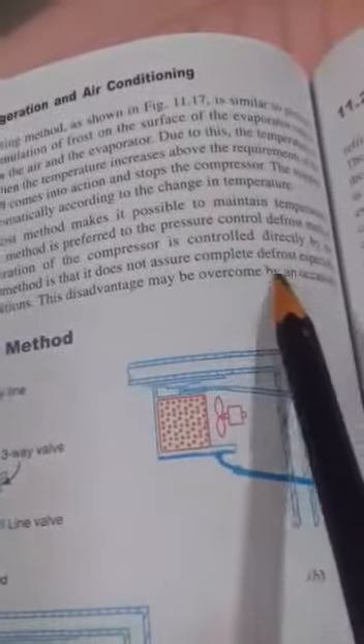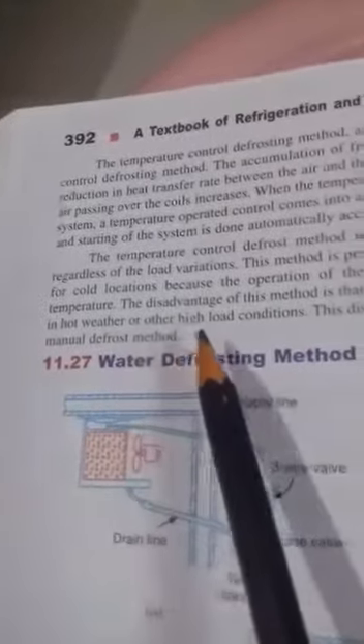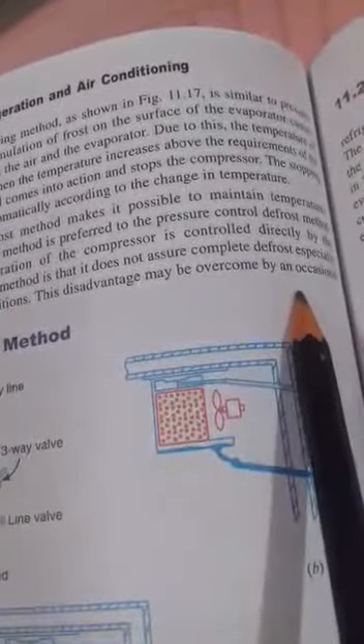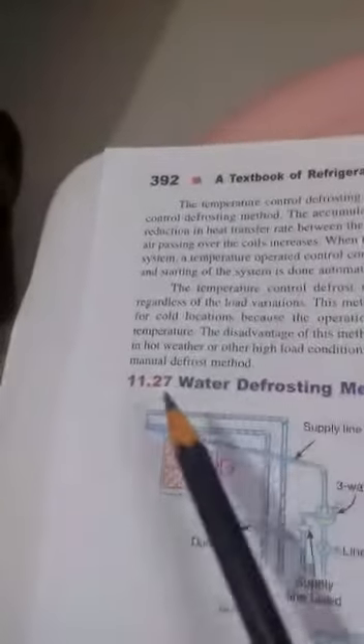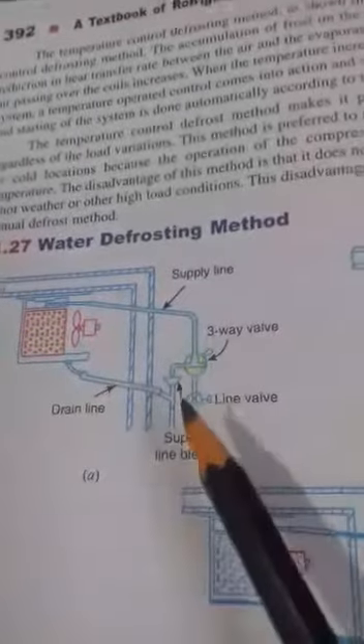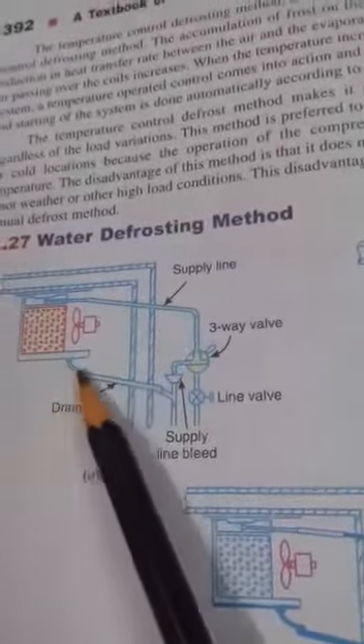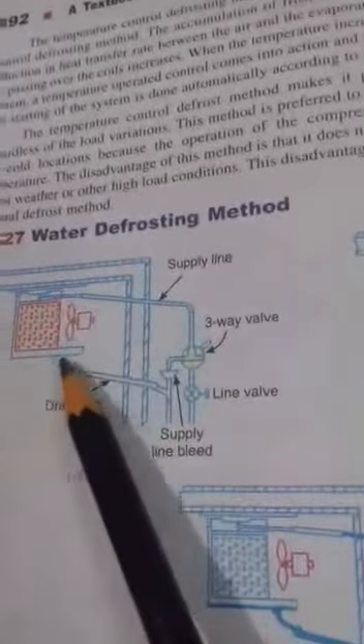This disadvantage may be overcome by occasional manual defrosting. For the water defrosting method, an operator uses a three-way valve which allows hot water to spray on the evaporator. After defrosting is complete, the water flows through a drain line. There is a supply line for the hot water and a drain line through which the water returns after being sprayed over the evaporator.